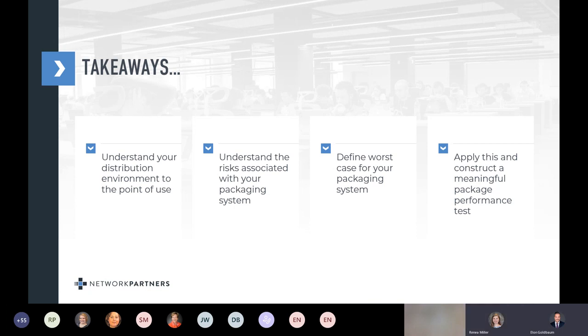Okay, great. Thank you. What would you consider worst case sterilization for package performance testing? Well, if it's within your process to, for example, do 2 times EO sterilization, so there's a chance that the product will be re-sterilized, then your worst case would be 2 times EO sterilization. And as far as the range of kilograys for gamma sterilization, you'd want to do the highest amount of kilograys for your worst case package testing.